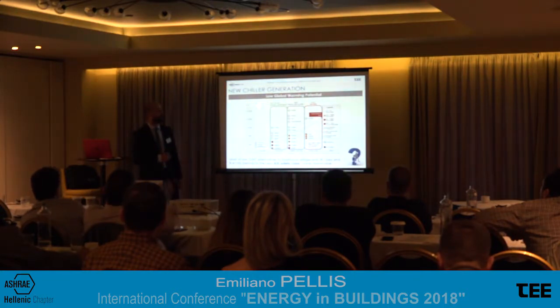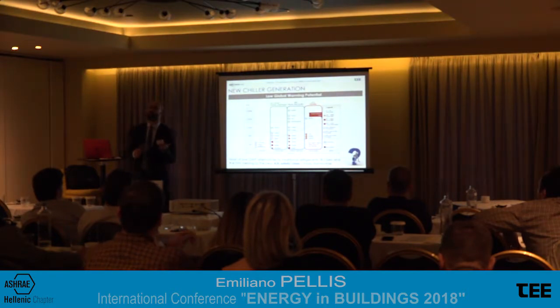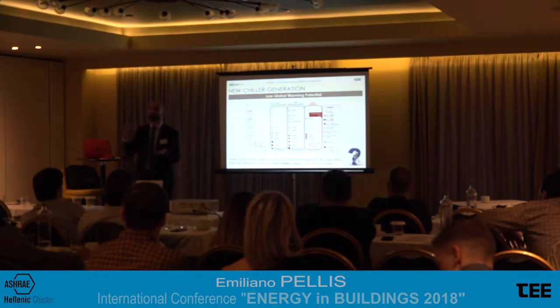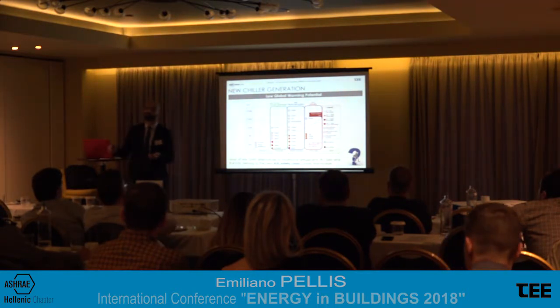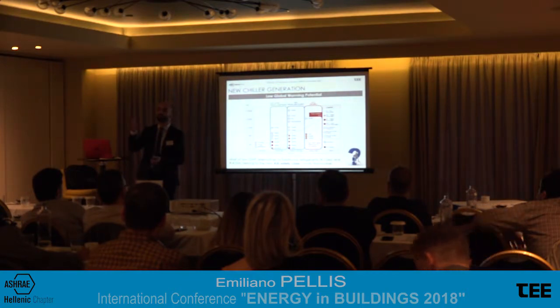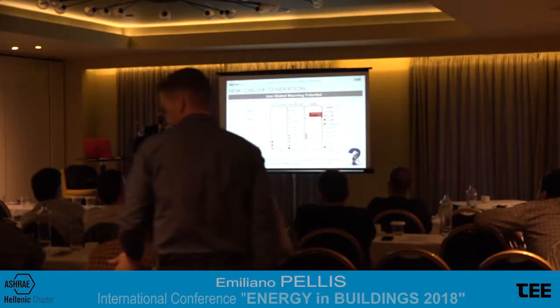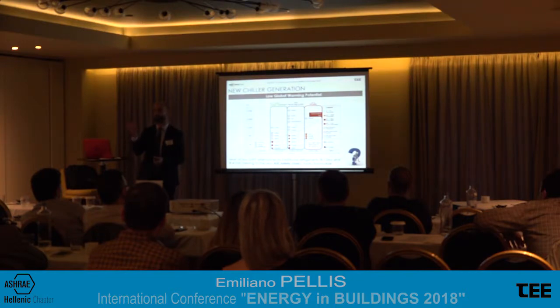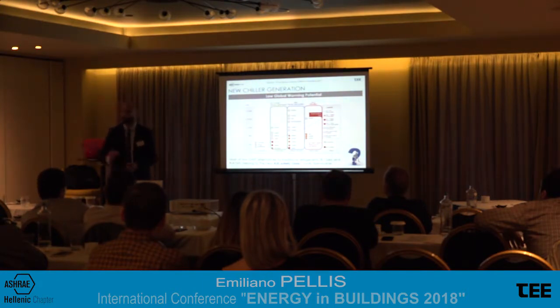Second step, low global warming potential. Okay, this is a chart. The message behind this chart is this. On one side, we have the traditional refrigerant, 134A and 410A. We want to move to new refrigerant with low GWP, but at the same time, we want to have good availability, good price, and also, of course, similar performance to 410A and 134A, because we like the 410A and the 134A, but unfortunately, we are obliged to move to something new.